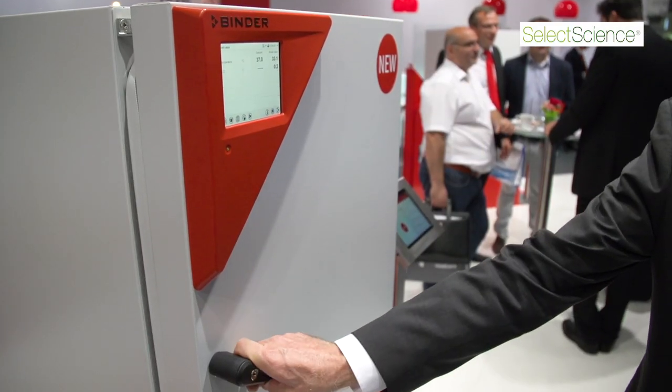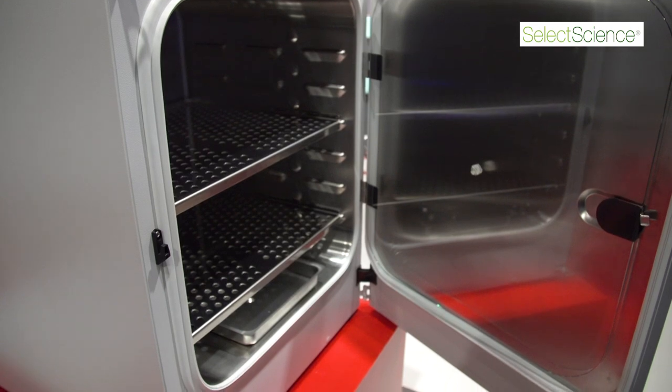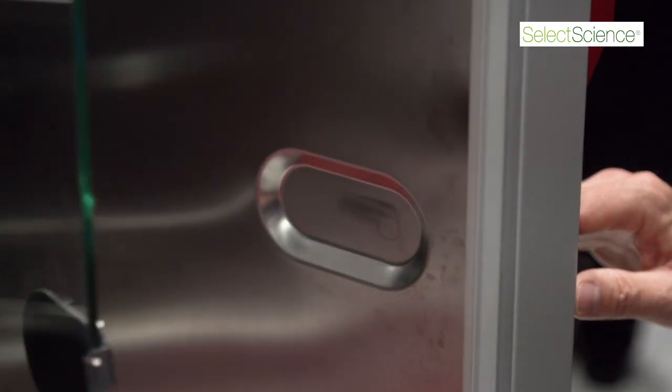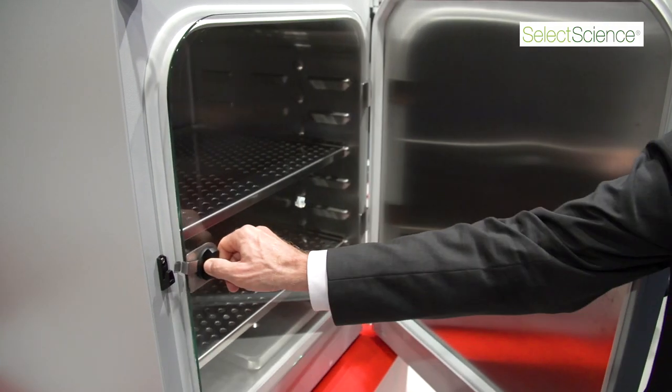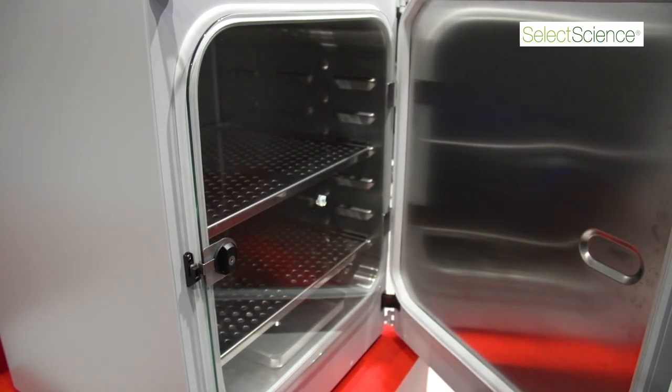Another difference is a new system called DUO-Door. The user has the choice to open both doors at once or one door after the other. Finally, we employ an infrared absorption CO2 sensor which is sterilizable and can be removed from the back, so serviceability of that part is great.